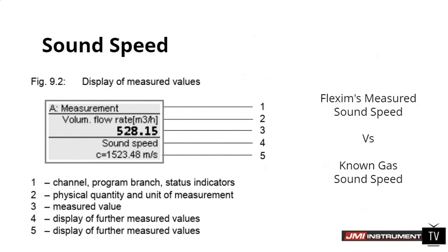So the other important diagnostic that we want to look for is sound speed. The sound speed of natural gas is generally around 400 meters per second, depending on pressure and the makeup of the gas. So that's a good diagnostic. What this diagnostic does is it tells you that you've installed the meter correctly. That number can change if you put in the incorrect outside diameter, or the incorrect wall thickness, or if you mount the transducers and the spacing doesn't match what the meter asked for and you didn't tell it that you moved the transducers. Those three things are things we can control, to make sure that our sound speed matches what it should.